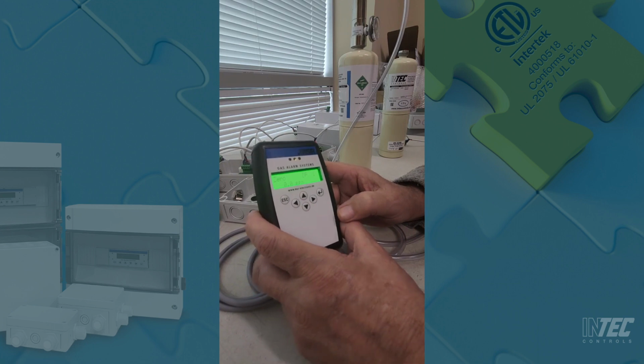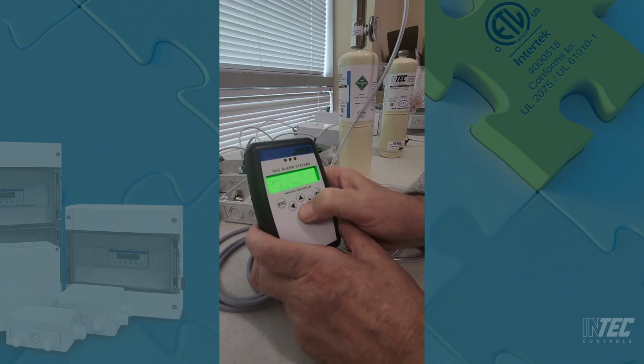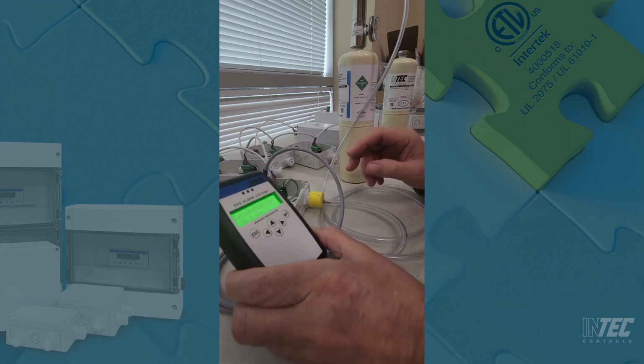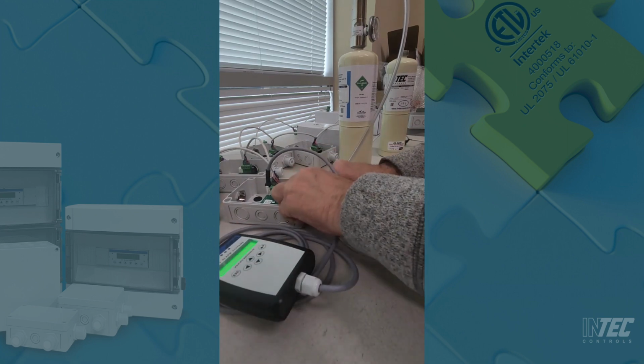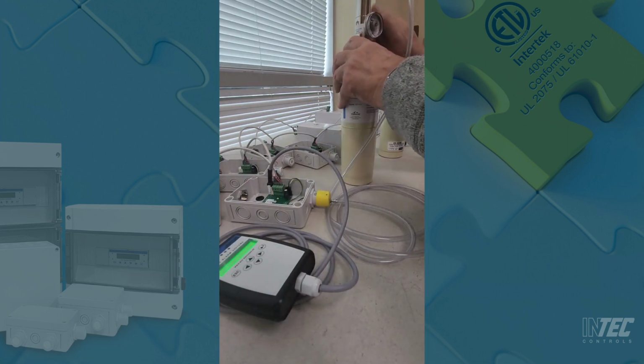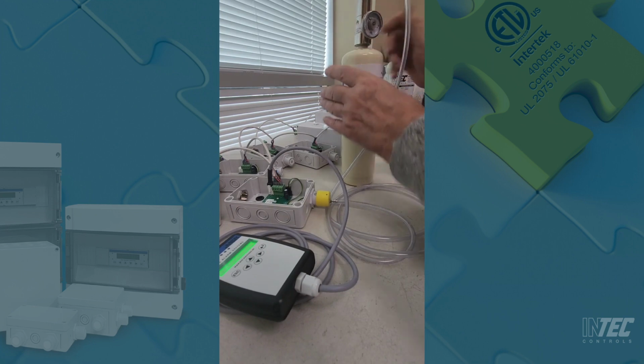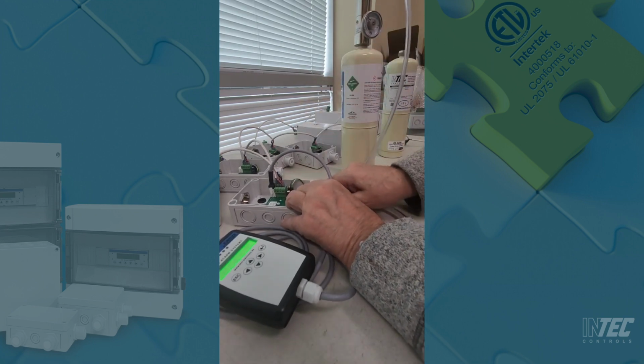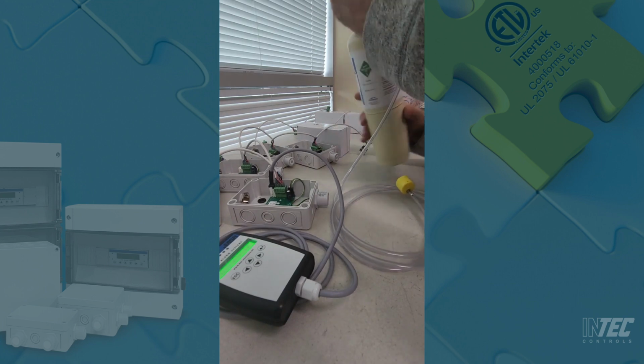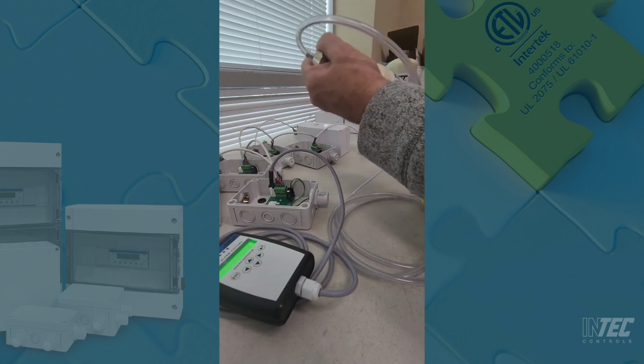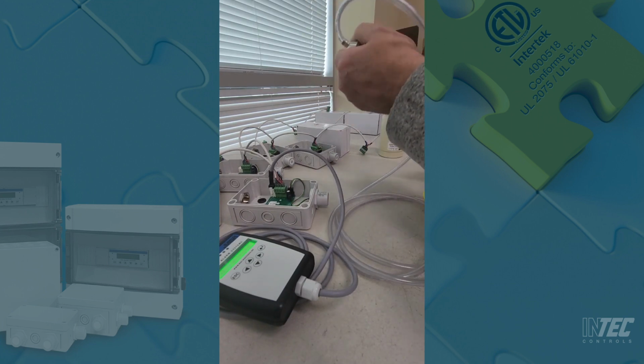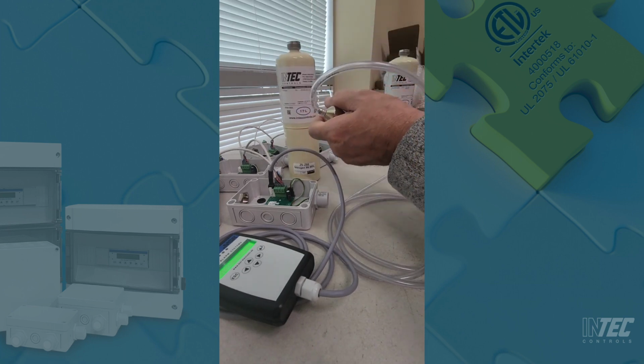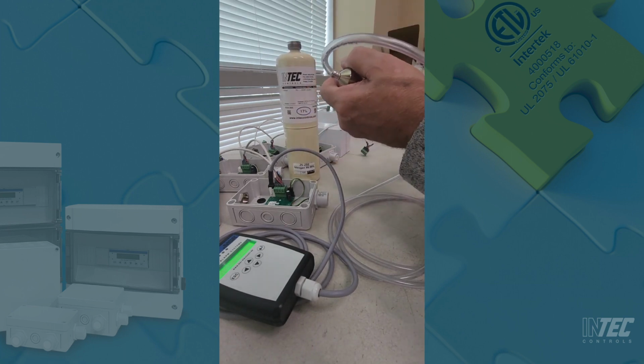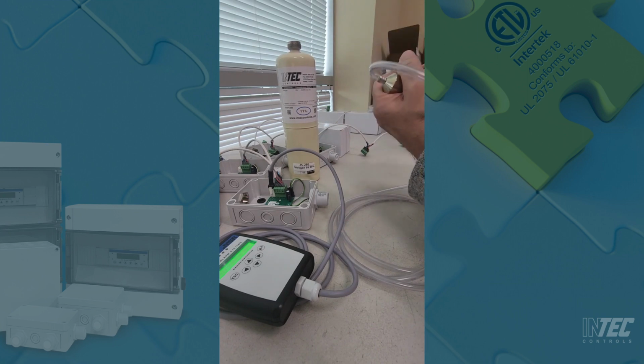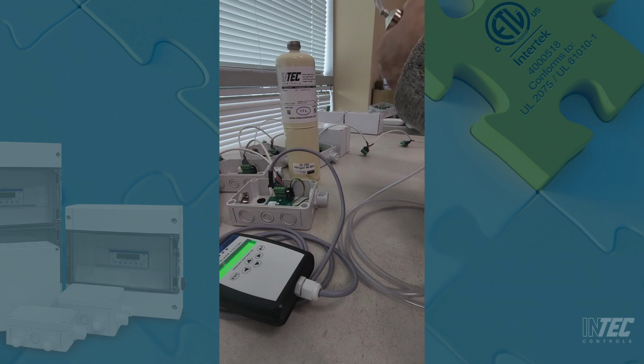All right, so at this point, we're done with the zero calibration. Now we're going to go to the calibration gas. So we're going to turn off our nitrogen, unplug our sensor cup from the sensor head, remove the regulator, and switch to our calibration gas, 200 ppm carbon monoxide. I'm going to screw this on.